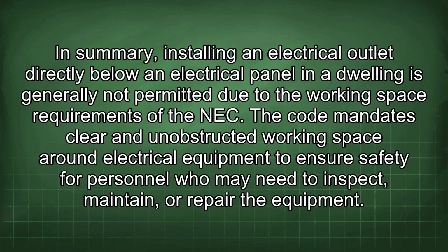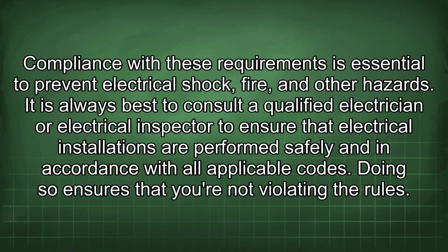In summary, installing an electrical outlet directly below an electrical panel in a dwelling is generally not permitted due to the working space requirements of the NEC. The code mandates clear and unobstructed working space around electrical equipment to ensure safety for personnel who may need to inspect, maintain, or repair the equipment. Compliance with these requirements is essential to prevent electrical shock, fire, and other hazards.